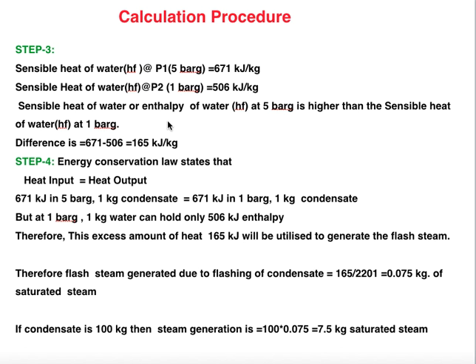Therefore, steam generated due to flashing = 165 / 2201 = 0.075 kg of saturated steam per kg of high pressure condensate. That means 1 kg of condensate at 5 bar gauge and 140°C generates 0.075 kg of flash steam at 1 bar gauge (120°C). If condensate flow is 100 kg, the flash steam generation is 100 × 0.075 = 7.5 kg of saturated steam.